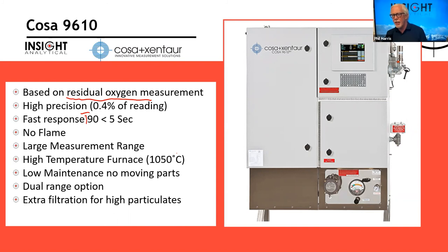We adjust that airflow rate for the changes that are happening in the fuel. Some residual oxygen analyzers historically had an open flame. The COSA does use a high temperature furnace running around 1,050 degrees C. There's no open flame there. It basically is a furnace oxidation of this fuel. And this has some safety advantages, certainly. Low maintenance, no moving parts, large measurement ranges, so we can cover a wide range of BTUs with appropriate calibration. We can put in a dual range option in case you do fuel switching. And we can add a bunch of extra filtration for different types of fuels. If they have particulate loading, fines in them and things like that, we can add some extra filtration for those.